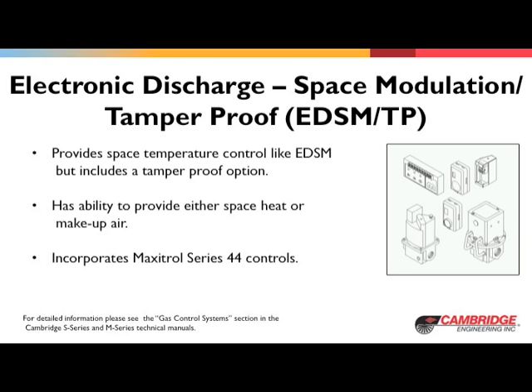EDSM/TP incorporates Maxitrol 44 series controls. The components utilized are a Maxitrol A1044 amplifier, a TS-144 discharge temperature sensor, a TD-244A space temperature selector, a TS-244A tamper proof sensor, and either a Maxitrol MR212, an M511, or an M611 modulating valve.